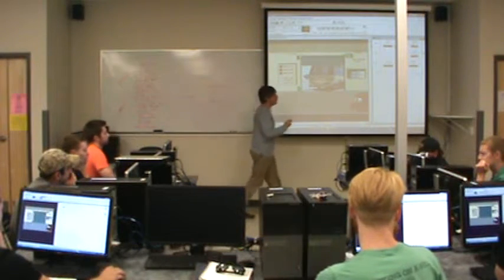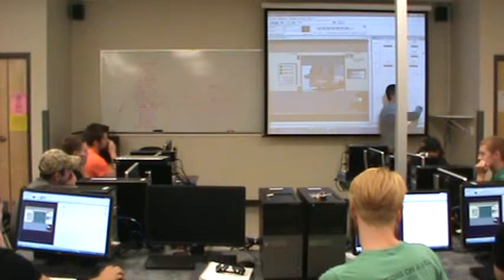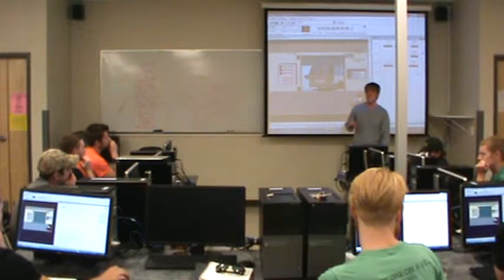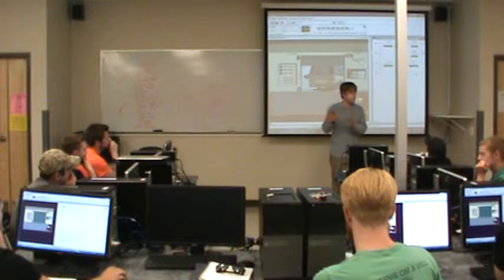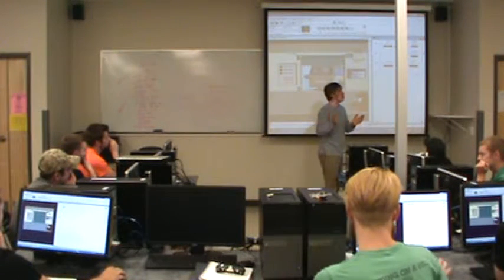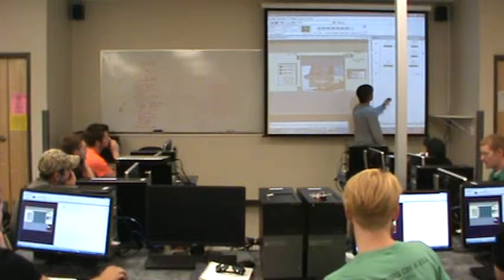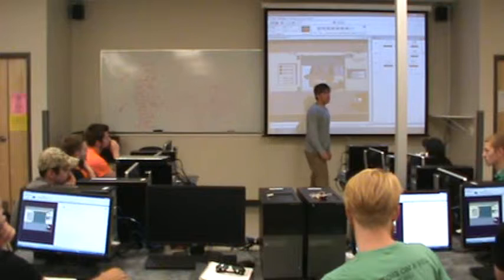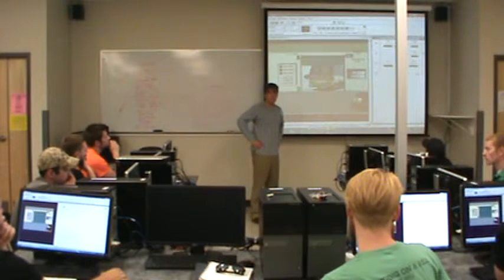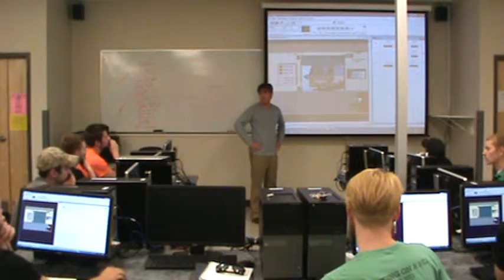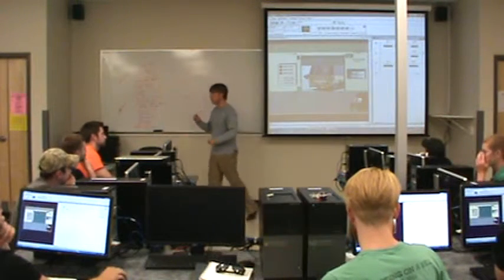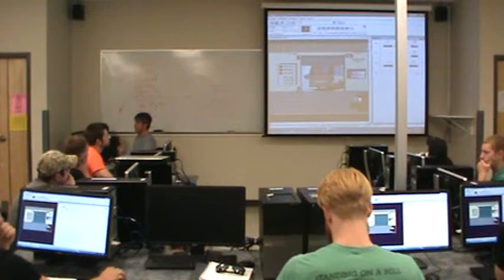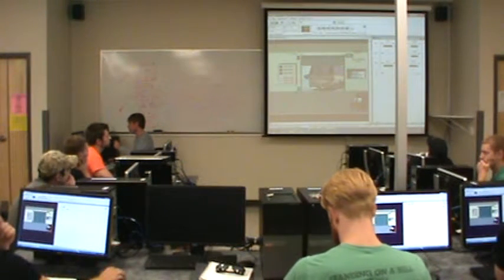Okay? So you have to be careful with that, and that's one reason I don't like the latch and unlatch for learning PLC programming. Now there are really good places to use the latch and unlatch when you're just trying to turn a bit on and remember that something's happened. That's a great place to use it. Okay? Well, we'll get to that later. So for right now, when would I want to turn the motor off going up? When it's reached the top. Right? So when it clears the limit switch. So what I really want is when the upper limit switch goes off, I want to activate turning off the motor up. Is that confusing enough yet?